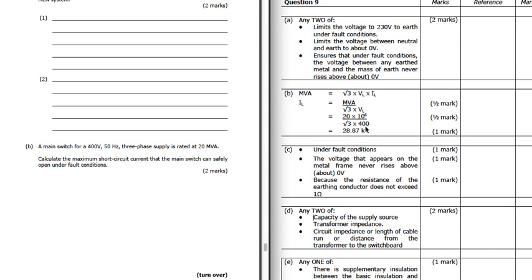So there's our √3. We're told it's 400 volts. So it's 20 times 10 to the 6, because this mega is 10 to the 6, and that gives us 28.87 thousand amps, kiloamps. So extremely high fault current that it can interrupt.